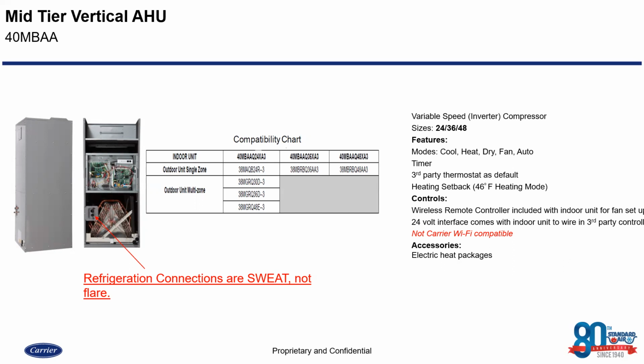However, if you look in the depiction of the vertical air handler in the electrical section, you'll see a little white device in there, which is an infrared receiver panel, which makes it compatible with a wireless remote controller. However, if that's not in the space where the customer is going to be at, then they're not going to be able to control via a wireless remote controller, which is going to allow you to have that heating setback feature, as you can't do it through a third-party thermostat, such as a Honeywell or an Ecobee, just because they don't have that option on there.